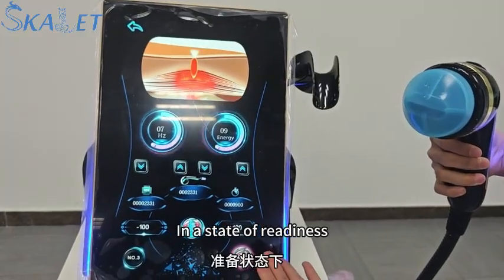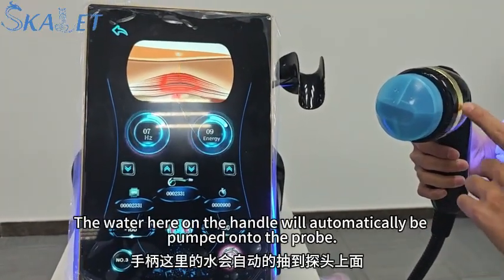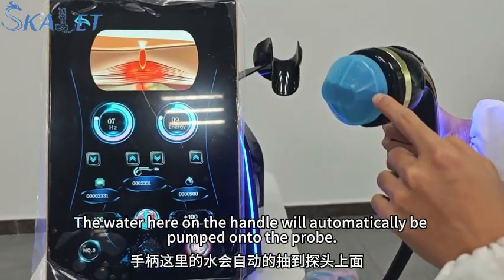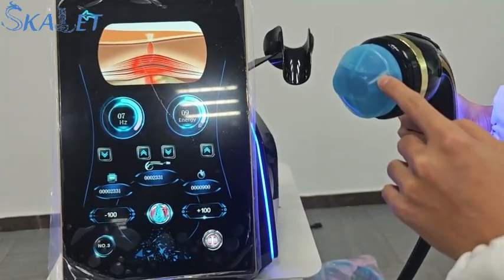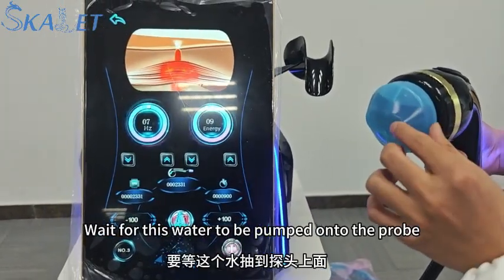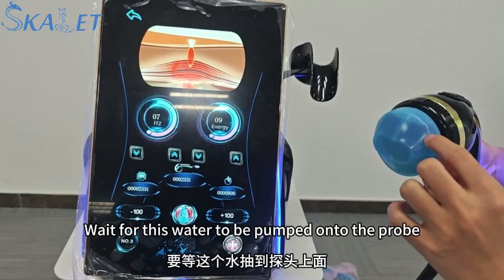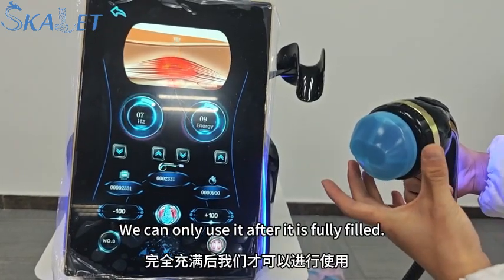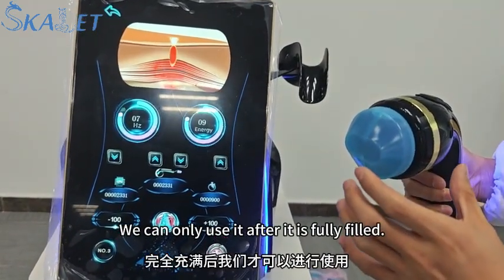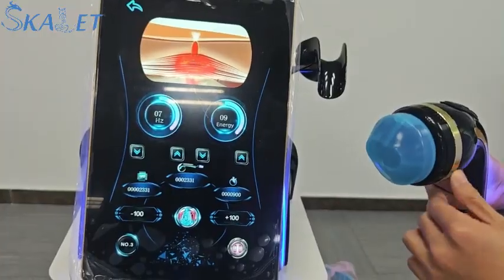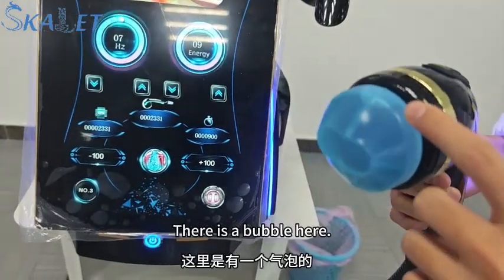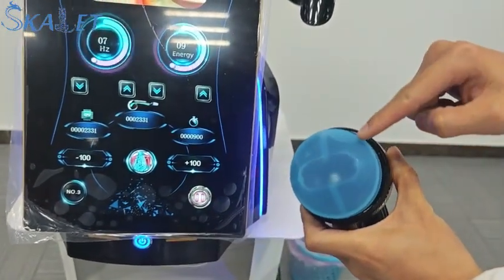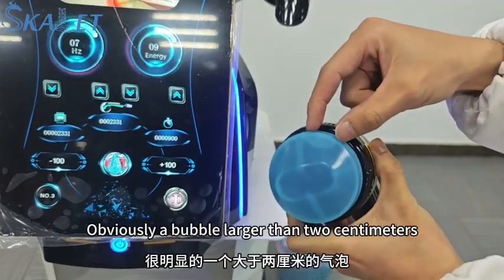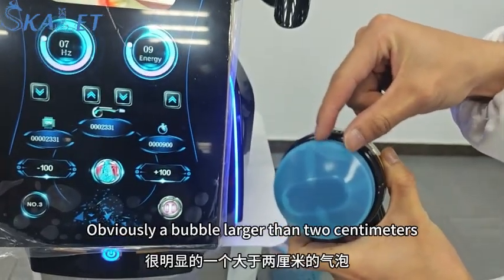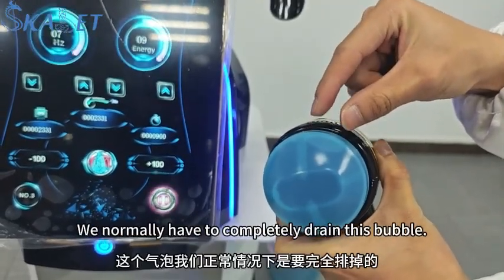In a state of readiness, the water here on the handle will automatically be pumped onto the probe. Wait for this water to be pumped onto the probe. We can only use it after it is fully filled. We can now see there is a bubble here, obviously a bubble larger than 2 centimeters. We normally have to completely drain this bubble.